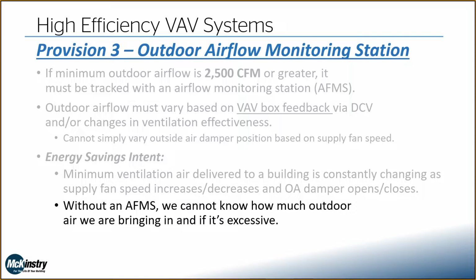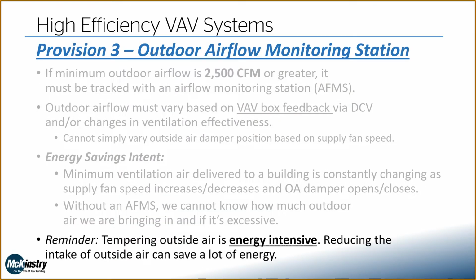And so if we have that airflow monitoring station, we know how much outdoor air we're bringing in and if it's excessive. Just as a general reminder, anytime we're tempering outside air, that takes a ton of energy. If it's 0 degrees outside in the middle of winter, which we can get to in Spokane, it takes a ton of energy to heat that outside air up. So anything we can do to reduce that intake can save us a lot of energy.